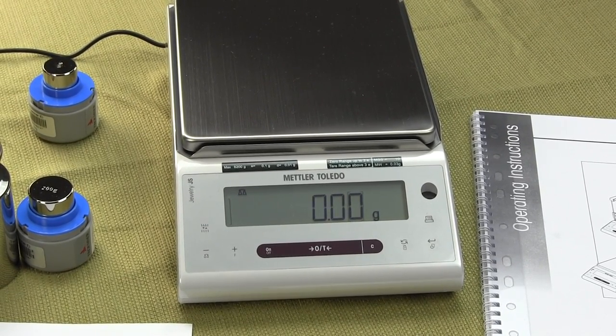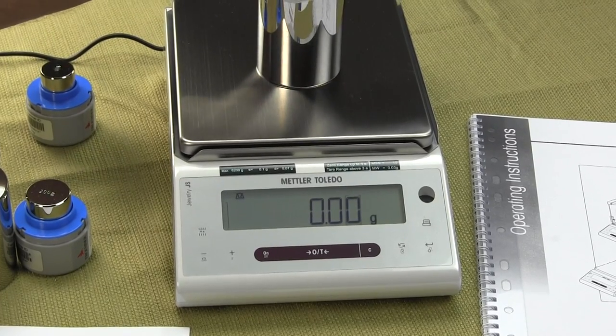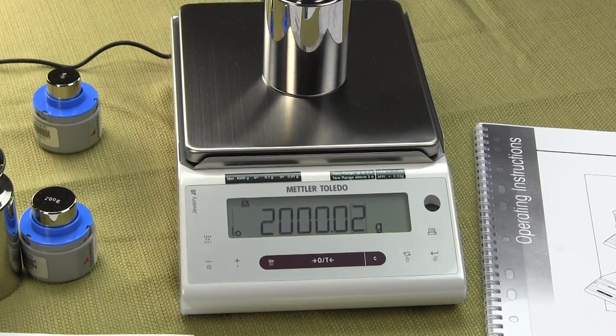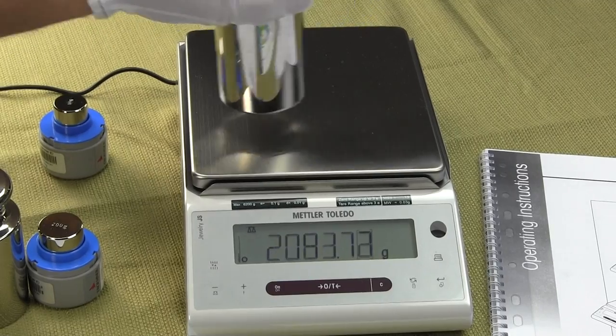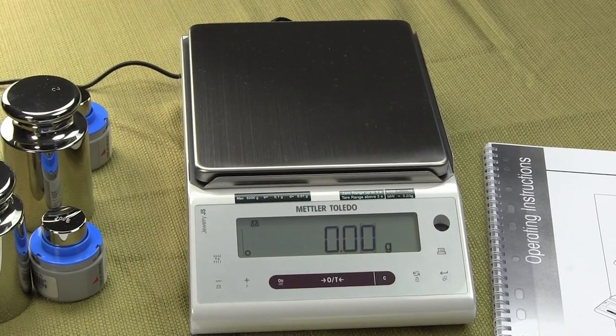The Slash A means it's legal for trade and this balance is 6200 grams by a hundredth of a gram.